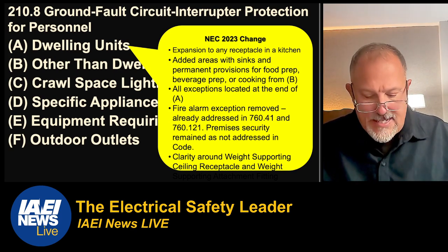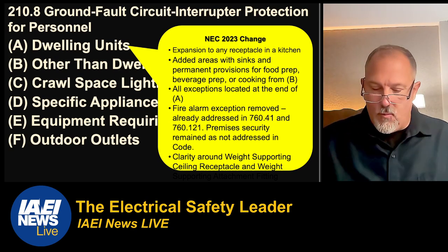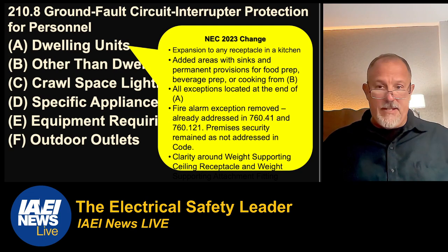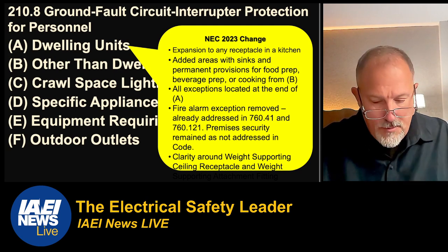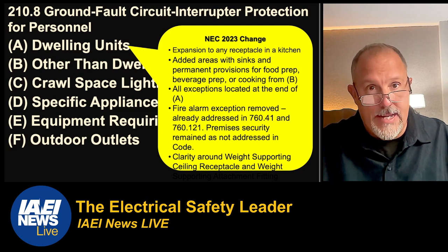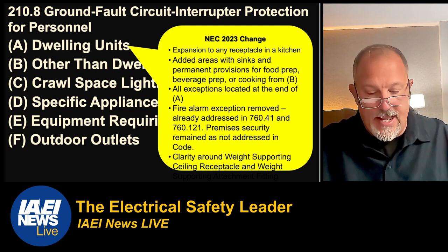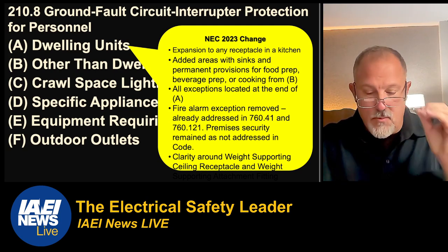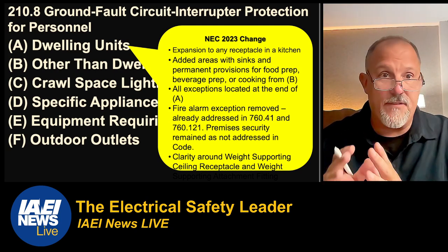In the exceptions, they added new definitions for weight-supporting ceiling receptacles and weight-supporting attachment fittings — basically a terminology change, the concept is the same. Those were the changes in 210.8A. The most significant change in 210.8A for dwelling units is the kitchen expansion — all receptacles in a kitchen, regardless of whether they serve the countertop, must now be GFCI protected.